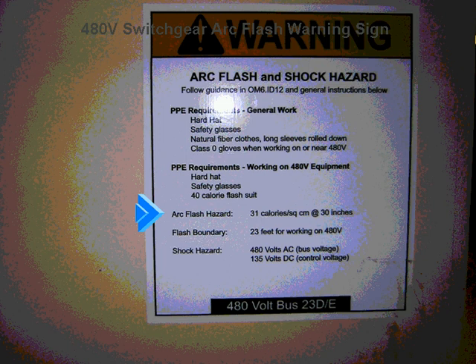I think this is an excellent picture. Again, a picture is worth 1,000 words. This is a sign actually taken at a nuclear plant out west. This is 480 volt switchgear, and they went through and performed an arc flash safety analysis and posted right on their 480 volt switchgear. If you look down right in the middle, there are PPE requirements, and it denotes the calories per square centimeter, which is an arc flash hazard, and the flash boundary.